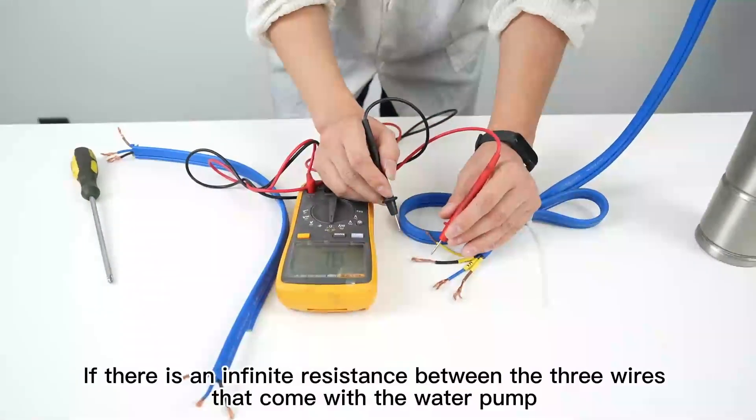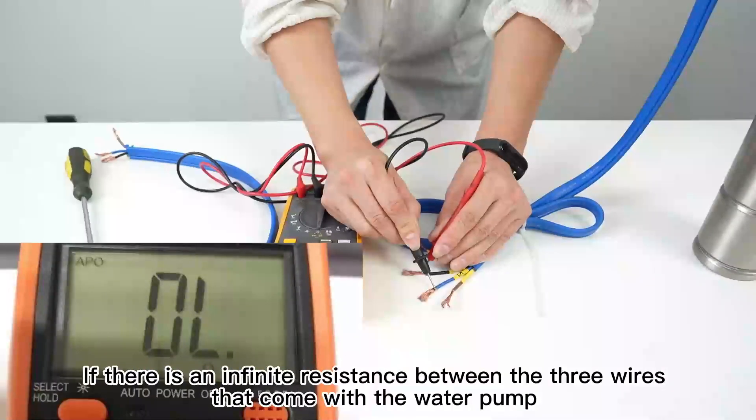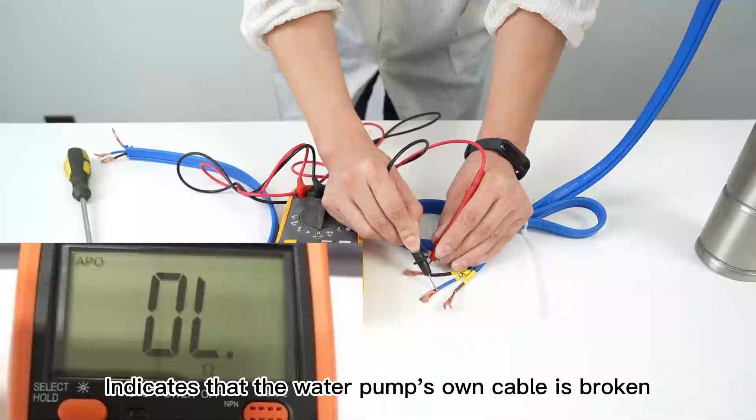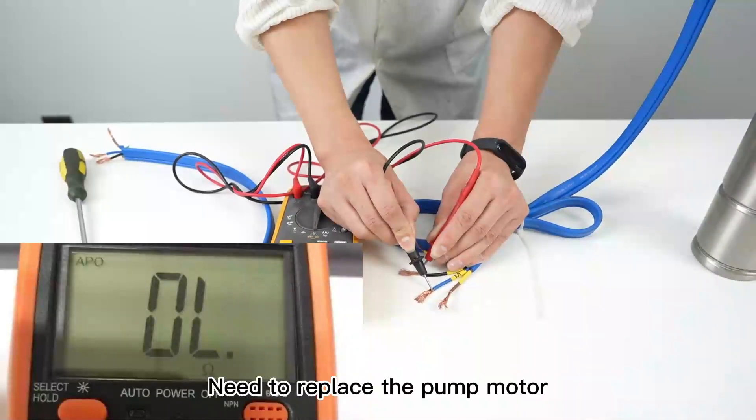If there is an infinite resistance between the three wires that come with the water pump, this indicates that the water pump's own cable is broken. Need to replace the pump motor.